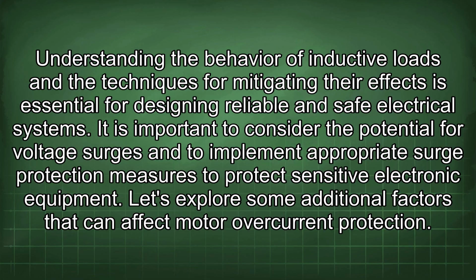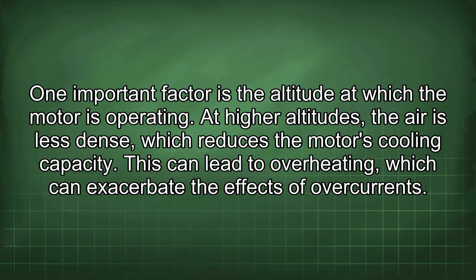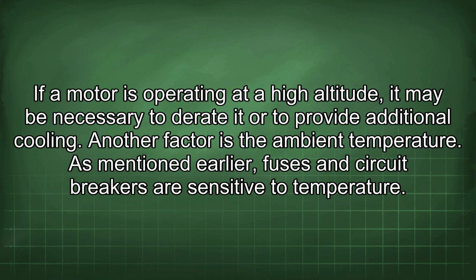electronic equipment. Let's explore some additional factors that can affect motor overcurrent protection. One important factor is the altitude at which the motor is operating. At higher altitudes, the air is less dense, which reduces the motor's cooling capacity. This can lead to overheating, which can exacerbate the effects of overcurrents. If a motor is operating at a high altitude, it may be necessary to derate it or to provide additional cooling. Another factor is the ambient temperature.